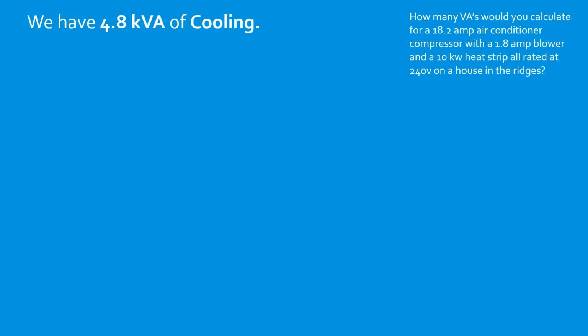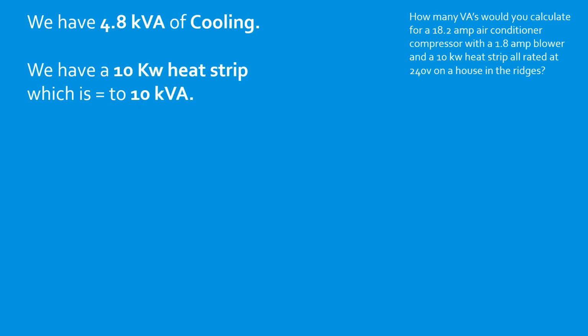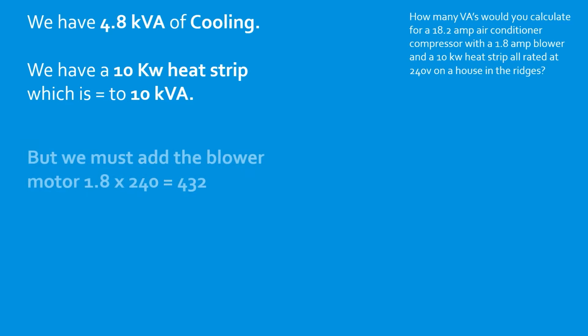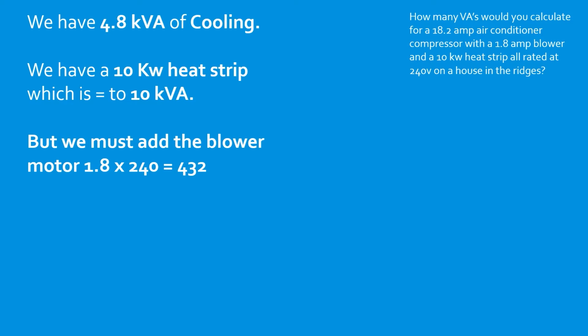All right, so we have 4.8 kVA of cooling, and we have a 10 kW heat strip, which is equivalent to 10 kVA. But we have to remember to add in the blower motor because it needs it too to blow the heat around. So we take our 1.8 amp motor and multiply it by the voltage, which is 240 volts. If we multiply those, that's going to give us 432 VAs that will actually add to our heat strip.